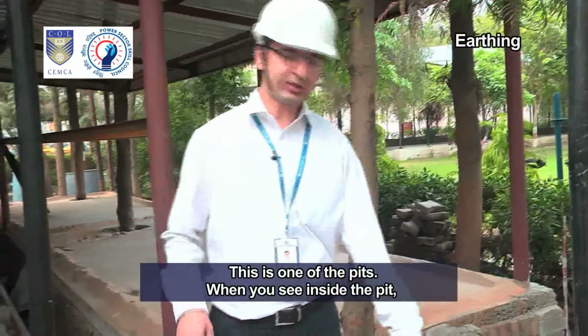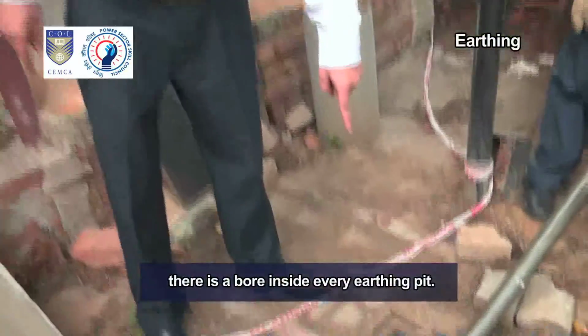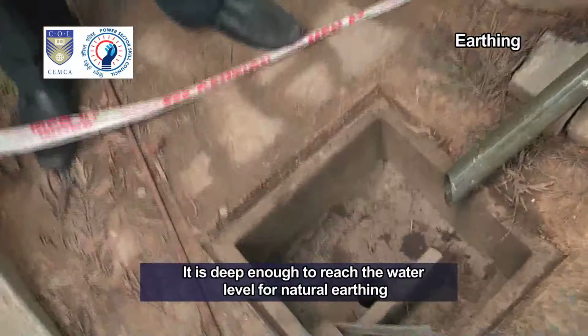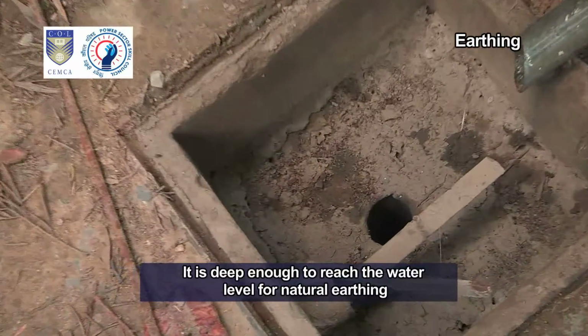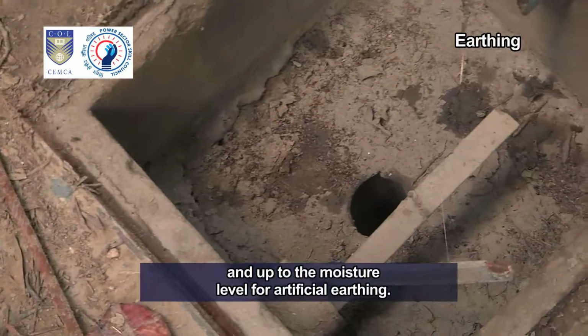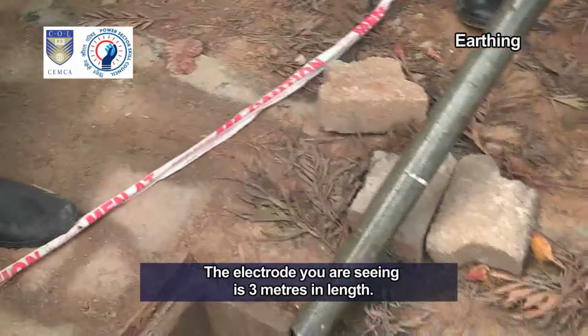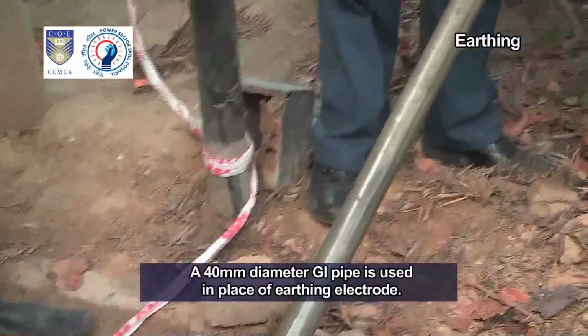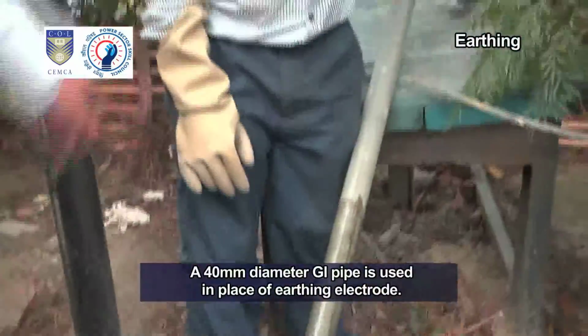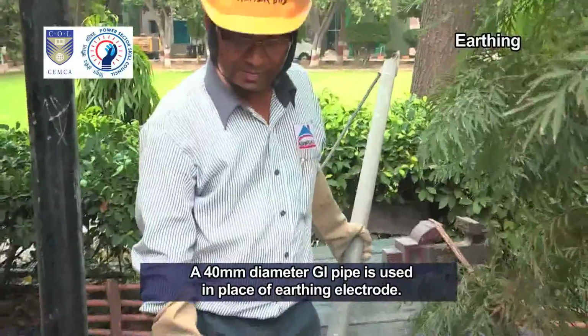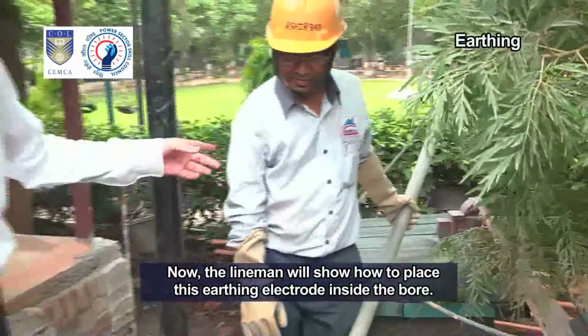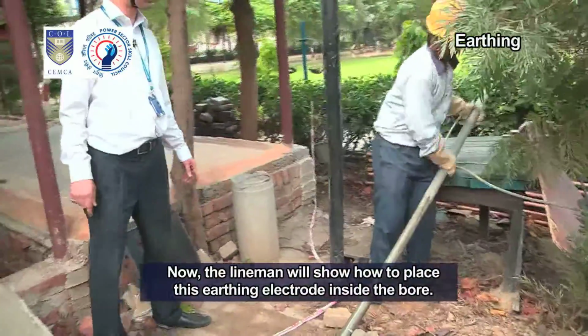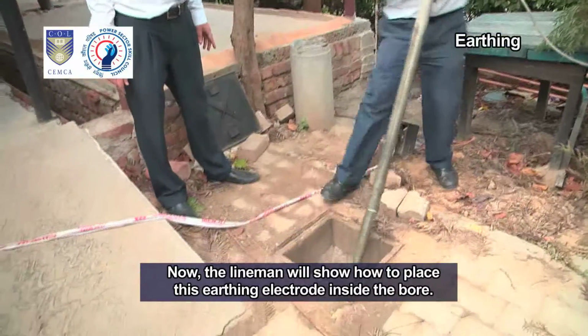When you see inside the pit, there is a bore inside every earthing pit. It is deep enough to reach the water level for natural earthing and up to the moisture level for artificial earthing. The electrode you are seeing is 3 meters in length. A 40 mm diameter GI pipe is used in place of an earthing electrode. Now, the lineman will show how to place this earthing electrode inside the bore.